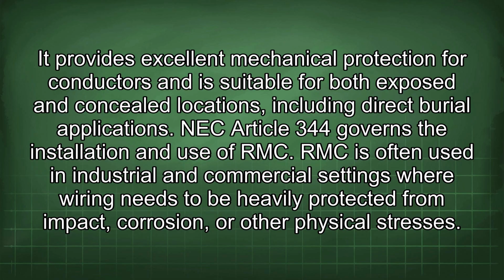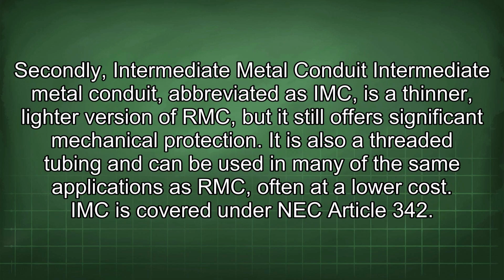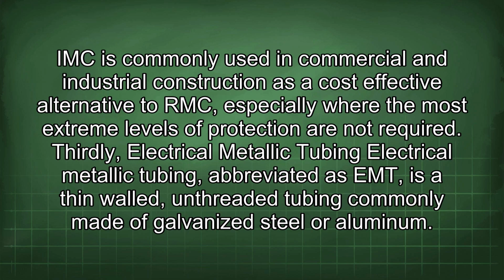other physical stresses. Secondly, intermediate metal conduit. Intermediate metal conduit, abbreviated as IMC, is a thinner, lighter version of RMC, but it still offers significant mechanical protection. It is also a threaded tubing and can be used in many of the same applications as RMC, often at a lower cost. IMC is covered under NEC Article 342. IMC is commonly used in commercial and industrial construction as a cost-effective alternative to RMC, especially where the most extreme levels of protection are not required.